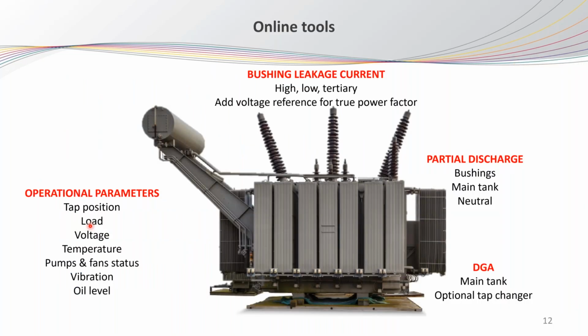For the online tools, these are the permanent sensors that we are putting on the transformers, and through these sensors we can monitor the condition of the bushing by placing a sensor to measure the leakage current. And we can also consider the partial discharge sensors that can be used to detect any PD activities. And of course, some sensors for the DGA to measure the dissolved gases inside the oil in the main tank, and if needed for the tap changer. In addition to these sensors, there are the operational parameters like the loading, voltage, and temperature, etc., to have a complete view on the health operation of the transformer.